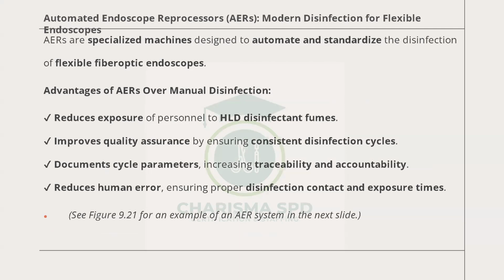Yes, so we have automated endoscope reprocessors, as I said. We use them for flexible scopes, and they are very helpful in the sense that they are enclosed. Once you put them in the machine, you close the lid, they are sealed. So you are not going to inhale or get yourself exposed to the chemical. After the washing is done, first of all, it will clean, and then it will disinfect, and then it will rinse.